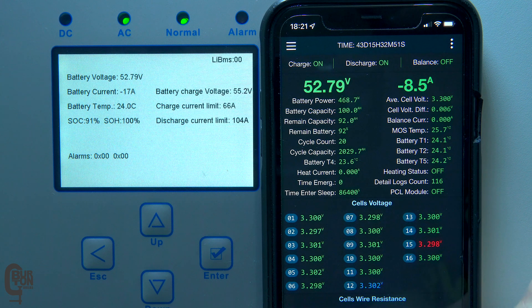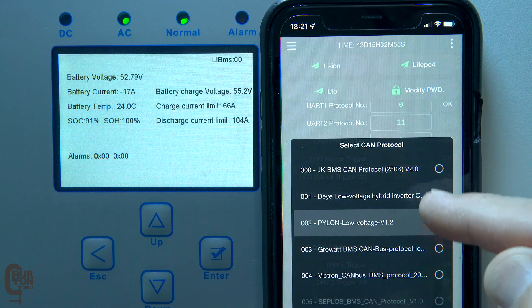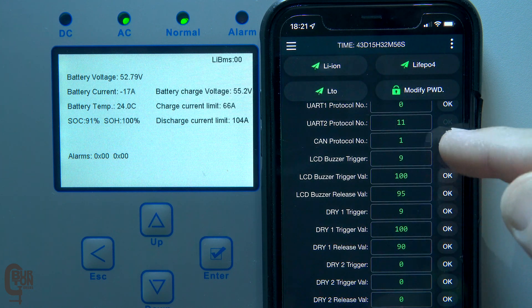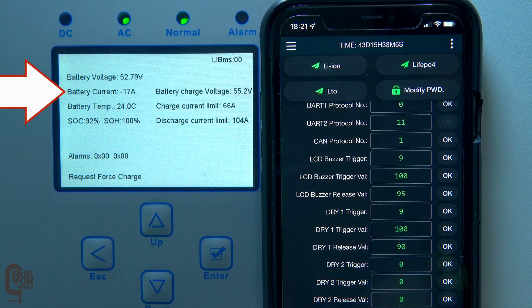In the settings on the master BMS, if I set the CAN protocol to 001 Deye low voltage hybrid inverter and save the setting, the request force charge command pops up on the inverter and you can watch the battery current go from discharging at 17 amps to charging at 36 amps.